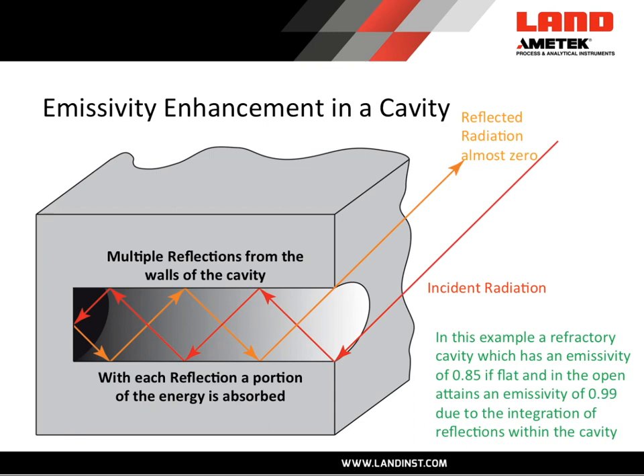Another way to raise the emissivity of a material is to change its shape. This is how people make black body calibration sources — they take a material like silicon carbide, which may have an emissivity value of 0.85, then produce a cavity within it of at least six diameters depth relative to the cavity diameter. The multiple internal reflections that occur within that cavity integrate together to give an emissivity value of almost one — in this example 0.99. Manufacturers produce black body calibration sources with emissivities of 0.99 or even 0.995.